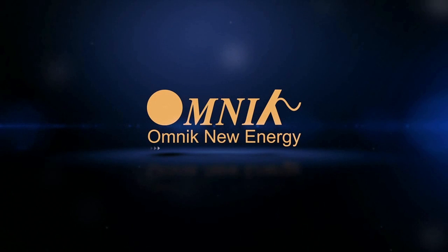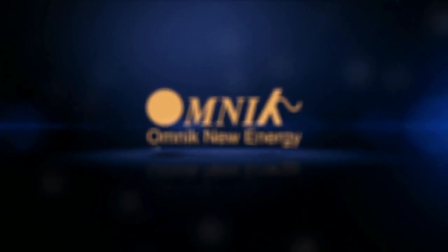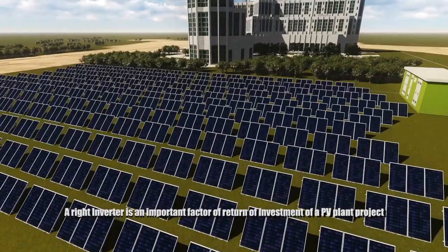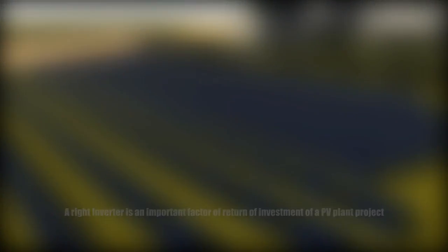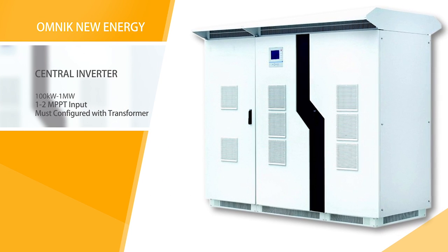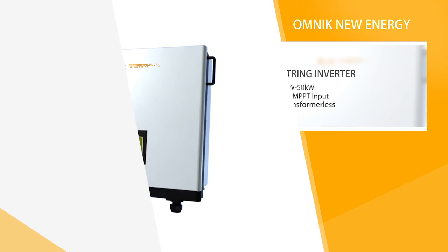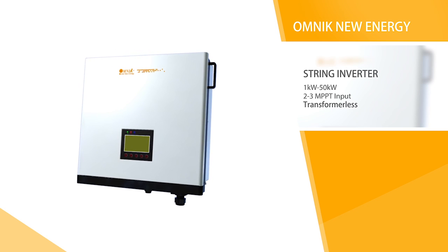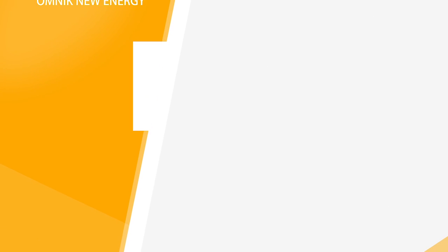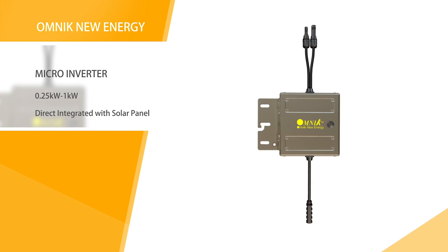Omnik lets mankind share and enjoy blue sky and white clouds. A right inverter is an important factor of return on investment of a PV plant project. In general, inverters can be divided into central, string, and micro inverters. Central inverters range from 100 kilowatts to 1 megawatt with one or two MPPTs, and a transformer is necessary. String inverters range from one to fifty kilowatts, are transformer-less, and have one, two, or three MPPTs. Micro inverters can be directly integrated with solar panels.